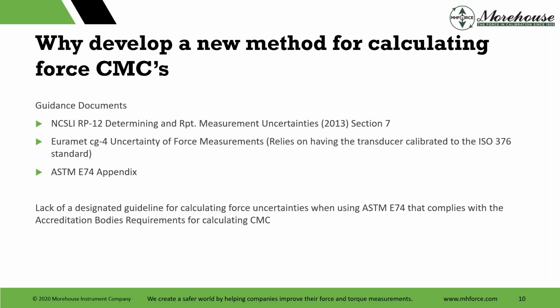So a lot of people in North America, and when I say numbers like a lot, that's pretty vague. I'm talking like 90-some percent of our business is calibration to E74, other calibrations, maybe 10% is ISO 376. So from our point of view, ISO 376 is used in North America, though by just a smaller percentage of people. So if you haven't heard about it, don't worry about it. It's probably not relevant to what you're doing unless you're in Europe or some of the other parts of the world. And then ASTM E74 has an appendix. It is a good start. There's some good recommendations in it, though it's not taking in degrees of freedom and all this other stuff. It's basically just RSSing, and it doesn't have all that you need.